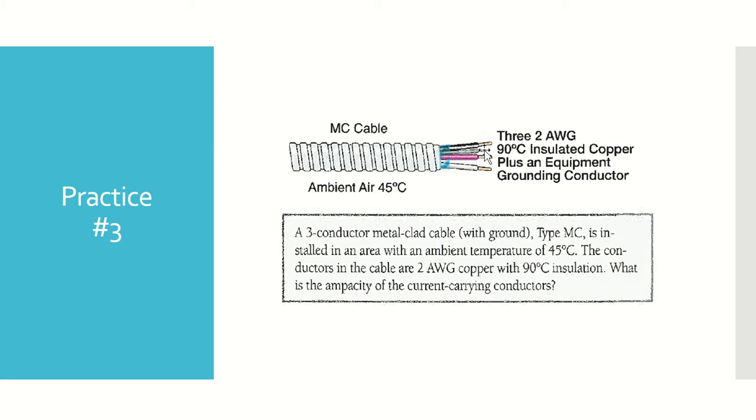We can eliminate that. And I guess I'm making an assumption when I say that, maybe they're using this for a three-phase piece of equipment, or I'm not sure if they're using this just for something where it's fed two phases with a neutral. So I think they're kind of vague in this example, but regardless, we can eliminate that equipment grounding conductor, and we know that we've got 3 or less. So we do not need to make any adjustments.